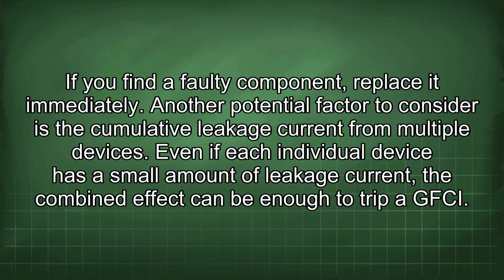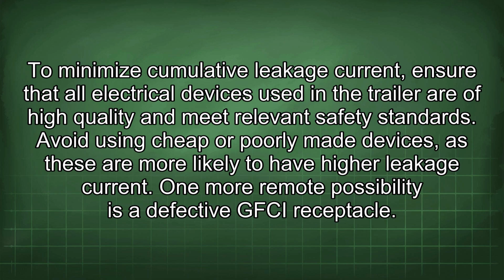Another potential factor to consider is the cumulative leakage current from multiple devices. Even if each individual device has a small amount of leakage current, the combined effect can be enough to trip a GFCI. To minimize cumulative leakage current, ensure that all electrical devices used in the trailer are of high quality and meet relevant safety standards. Avoid using cheap or poorly made devices, as these are more likely to have higher leakage current.